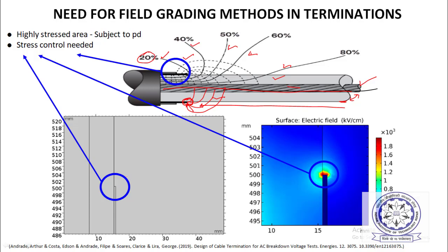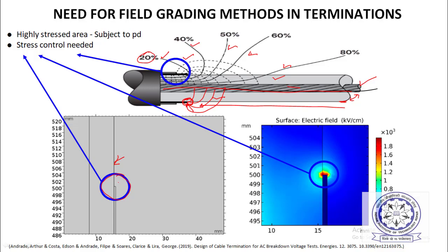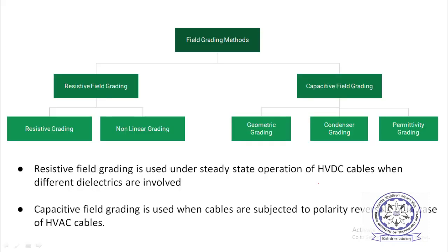Here you can see a cross-sectional view with the semi-con layer and the conductor. The simulated electric field distribution shows very high field — red color indicating above 1.8 × 10³ kV/cm — at the tip of the semi-conducting layer. This is how the electric field gets enhanced whenever we open the semi-conducting layer, and this creates problems and often breakdown also occurs at this junction.